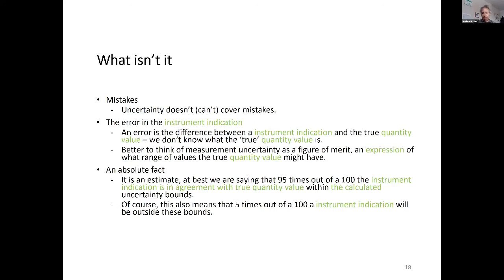And it is not an absolute fact. Because when we see the expanded uncertainty, this is why we say we have to evaluate it, but in the end, it is also an estimate: at 95%, or 66 and something percent, your measurement results lie within this range, plus or minus your sigma, let me say. And this also means that 5 times out of 100 you're out of that. So it's not an absolute fact. Again, you have to admit it, even when you're already uncertain.